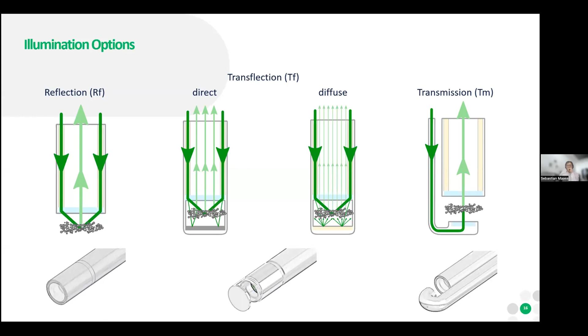So you're getting a lot of shadow information from the particles. They all have advantages and disadvantages. On this slide, just using one example here, the direct transflection shows you how you significantly influence the quality of the image by using different illumination options. Here we're decreasing the gap. Of course, with decreasing the gap, we're decreasing the volume in front of the probe, and by that, we're more or less decreasing the volume which will be analyzed, or which will be shined through with the light. The smaller the volume, the higher the contrast.